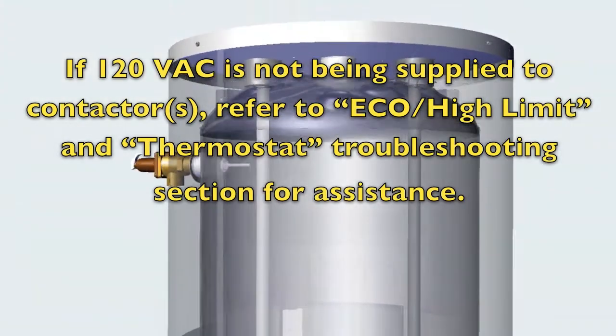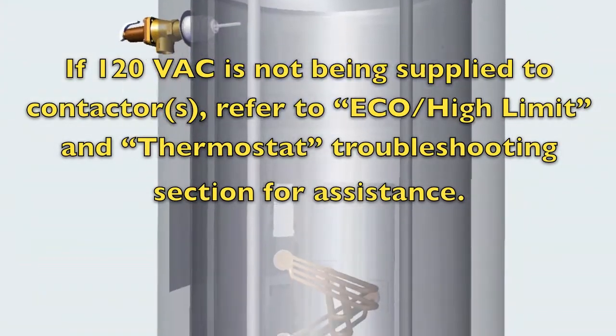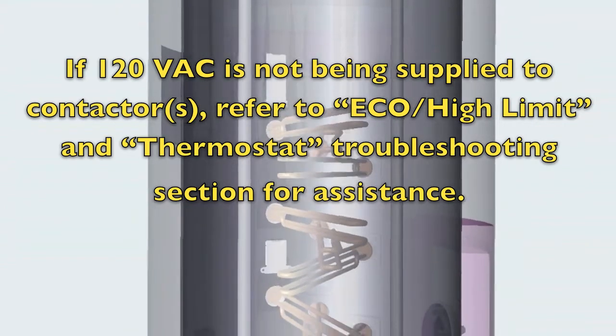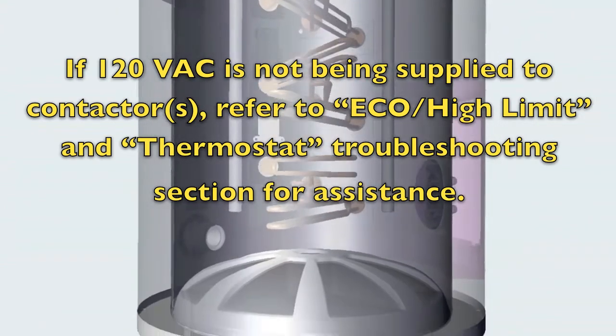If 120 volts AC is not being supplied to contactors, refer to ECO high limit and thermostat troubleshooting sections for assistance.